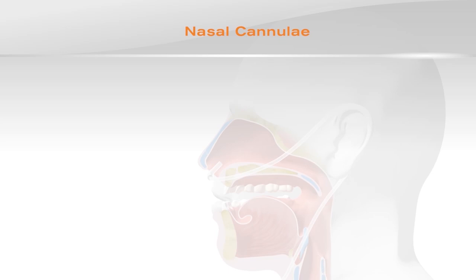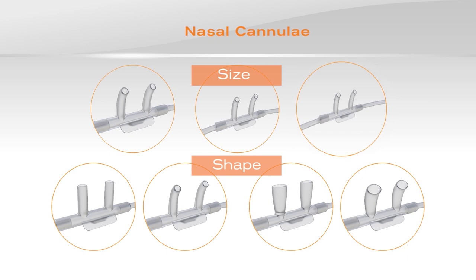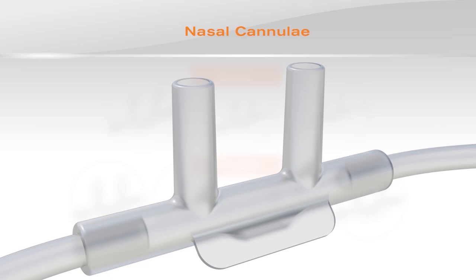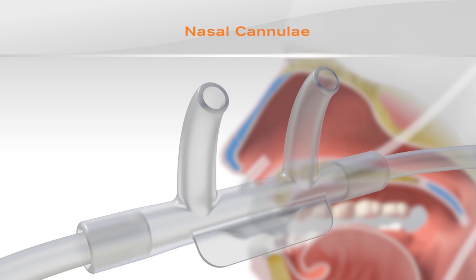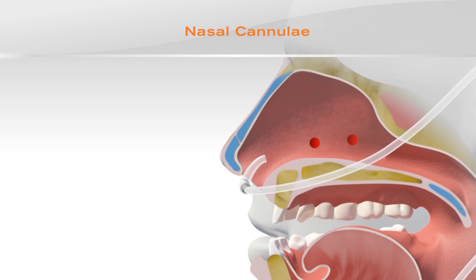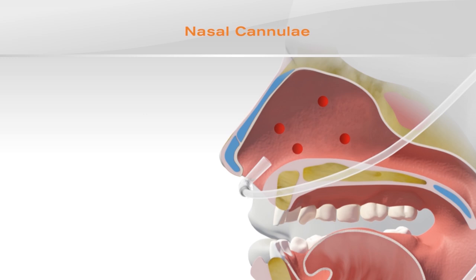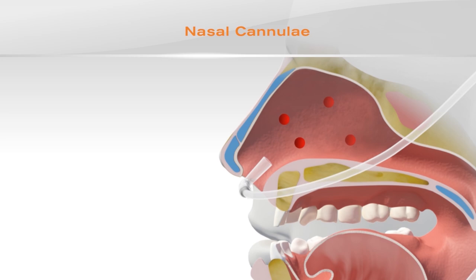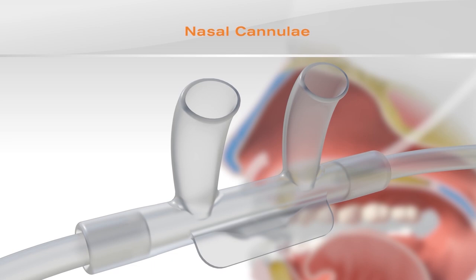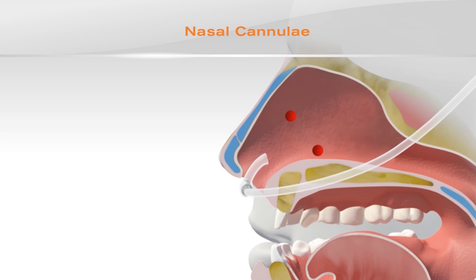There are various sizes available for adults, paediatrics, and neonates, and a variety of prong shapes are available to suit varying circumstances. Straight prongs are the original design and are still the most frequently used in hospitals. Curved prongs are designed to direct the flow of oxygen posteriorly rather than upward towards the frontal sinuses. Flared prongs have an increased diameter towards the tip, which has the effect of slowing down the gas as it enters the nose, making it more comfortable for the patient. Curved and flared prongs combine the best features of both options, releasing oxygen more slowly and away from the frontal sinuses.